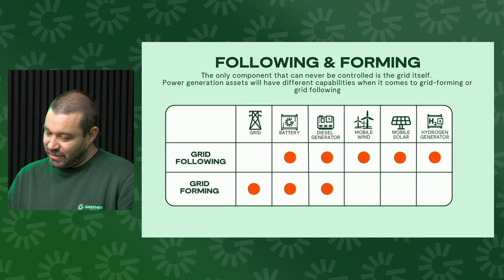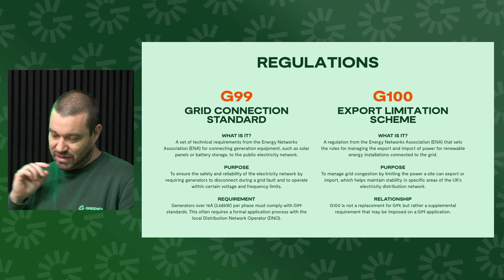Of course, while we're talking about synchronization and the grid, when the national grid is being used, we do need to look at the regulations in place. So we have G99, which is around disconnection under and over frequency or under and over voltage. You can look all of that up online, or there's some information on the slides that you can review later on. G100 is slightly different, more focused on energy import and export across a connection point on the grid, so there's again limitations in place that are all different across different connection points.